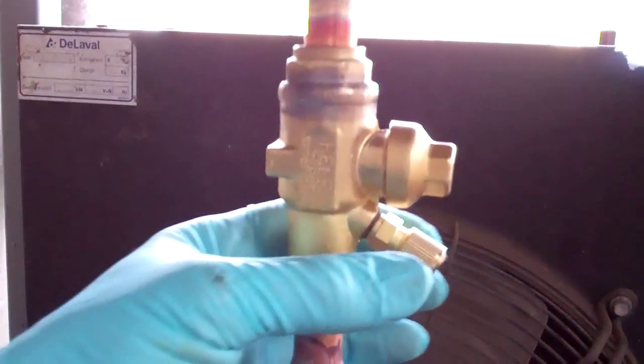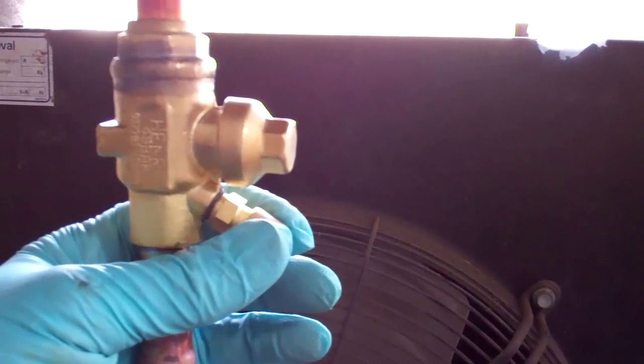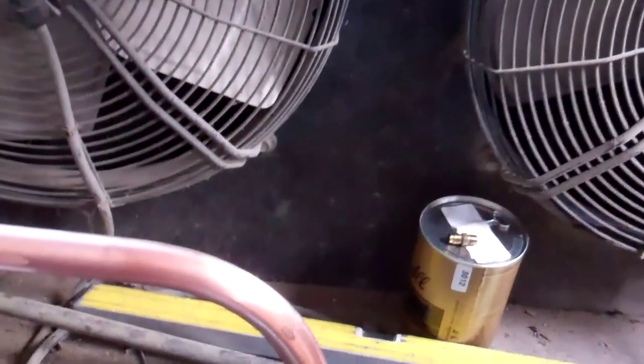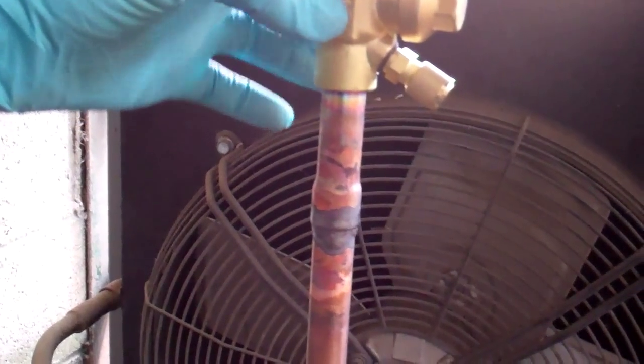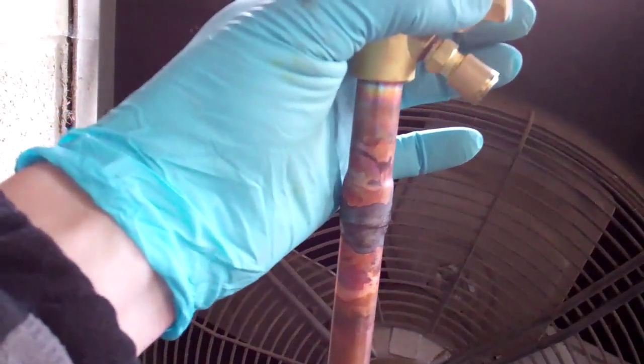We've got a ball valve there with a Schrader connection, so we can either pump it down and then shut this, and then we only have to vacuum out this little short bit of pipe up in the dryer shell. Or if it's got a lot of moisture in there and we can't pump it down because the expansion valve has frozen up, we can just shut this and recover the liquid out of there back into the compressor. And then we can change the dryer core and vacuum out from that point and carry on that way.